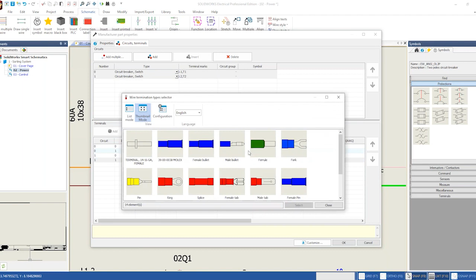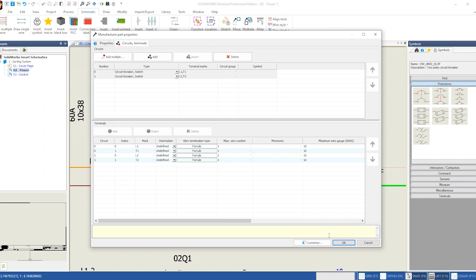Now, if this part needed an additional wire termination type, maybe I typically use wire ferrules, or the manufacturer specifies that I need wire ferrules, I can define that here also, and get that into a report. So I can say it requires a ferrule. Now, that's not going to add a manufacturer's part to the library for me, but I can use that as a way of checking stuff.